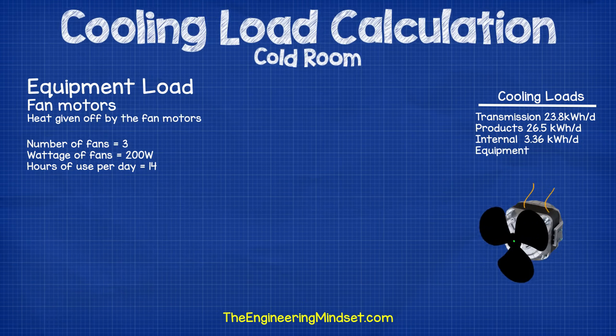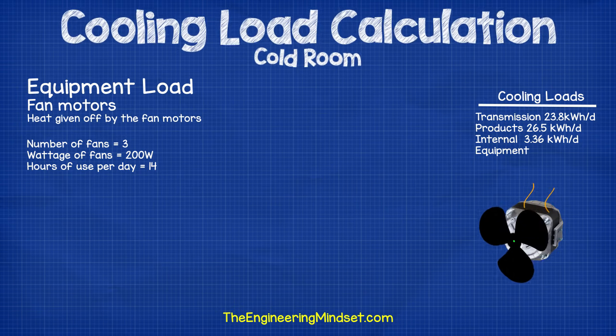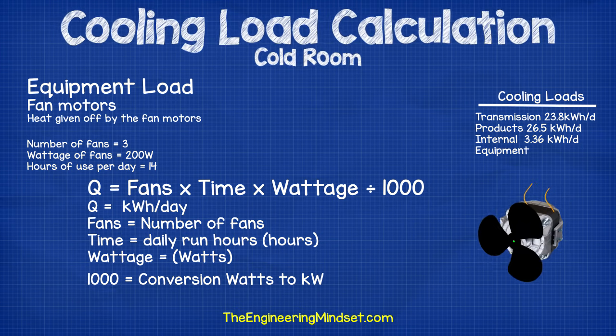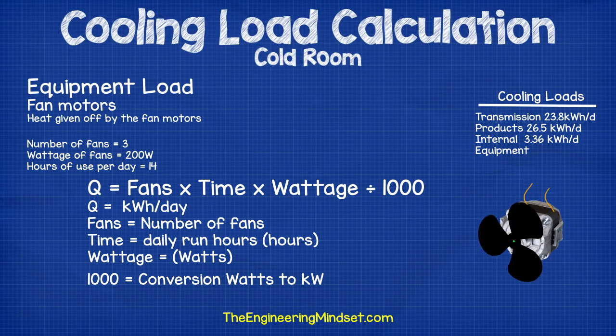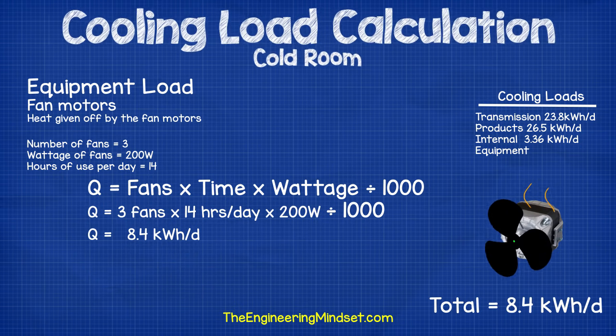Now we calculate the heat generation from the fan motors in the evaporator. In this cold room we'll be using three fans rated at 200 watts each, estimated to run for 14 hours per day. Using the formula q equals fans multiplied by time multiplied by wattage divided by 1000, where fans is the number of fans, time is daily run hours and wattage is the rated power of the fan motors, dropping those numbers in gives 8.4 kilowatt hours per day.